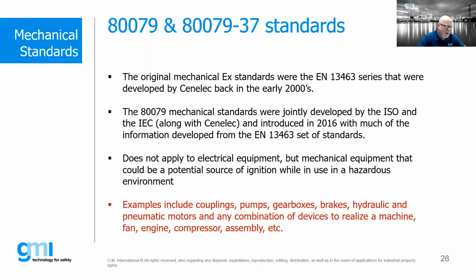We've talked about this in other webinars - when we look at the root causes of some of the big industrial accidents, we actually find that in many cases it wasn't necessarily an electrical issue that was the source of ignition. It could have been mechanical equipment. There are quite a few examples in industry where bearing failures or something non-electrical overheating has actually been the ignition source.